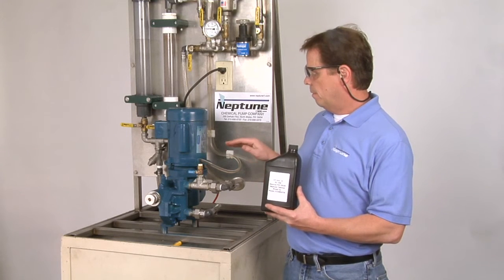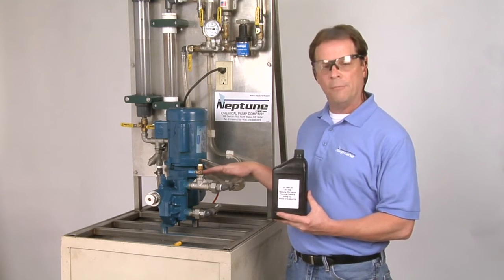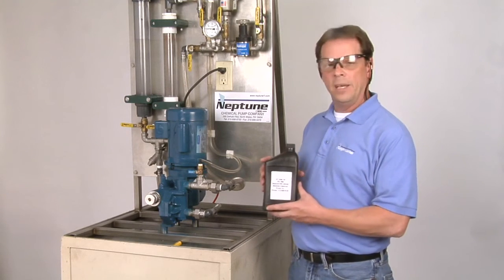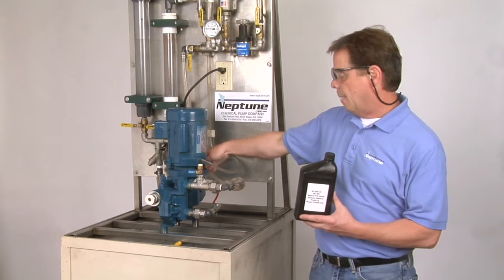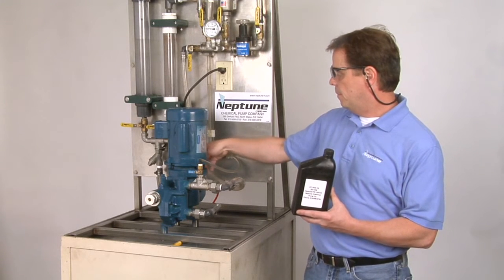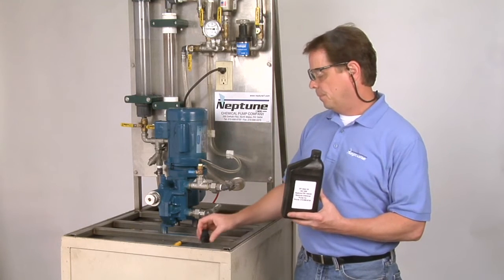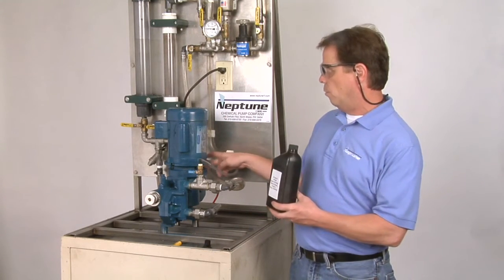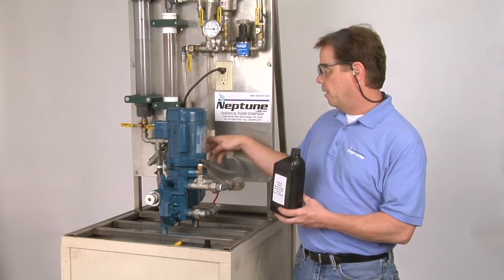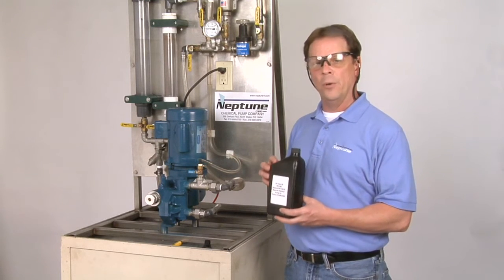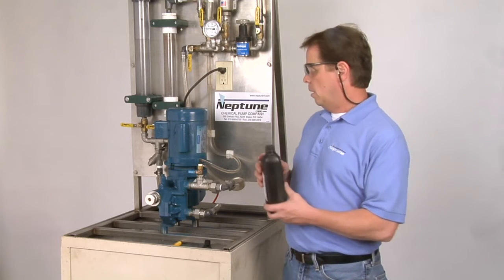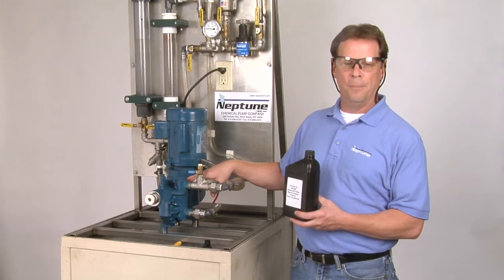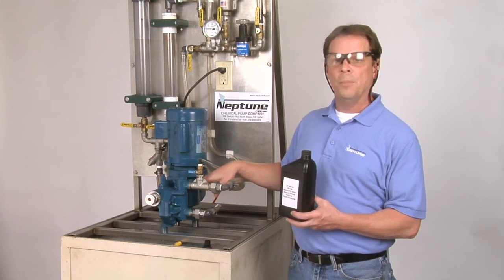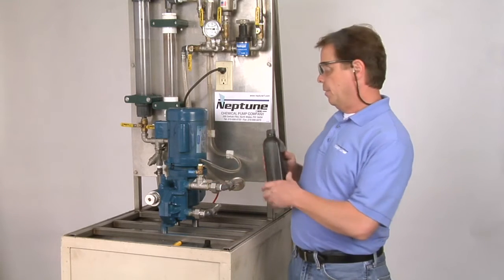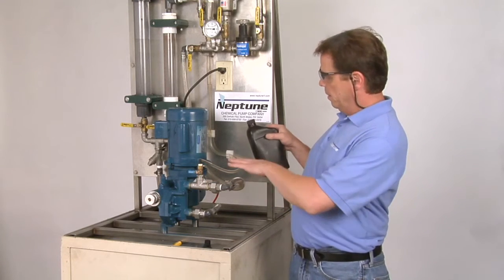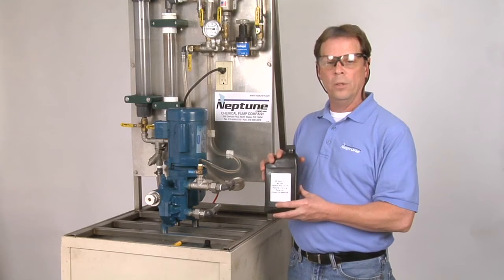You need to have so much oil in the pump for it to operate properly. When filling up the gearbox, you have your oil fill cap that's in the back of the pump. You'll see the oil fill cap. Remove it, and then you want to put the oil into the gearbox from the back. You want to be about 1/4 to 1/2 inch below the bottom fill thread hole, and basically you want to be above the piston that's in the pump. If you don't put enough oil in, the pump will not work properly. Now there's already oil in this particular pump, but again, using the correct amount of oil is critical.